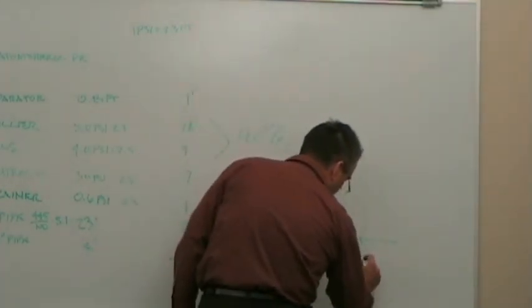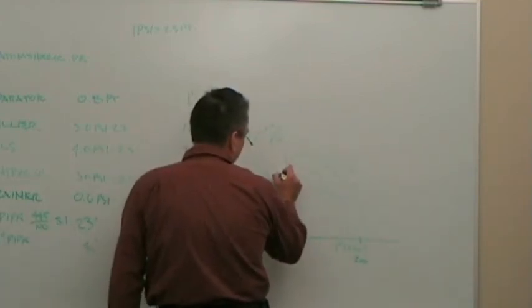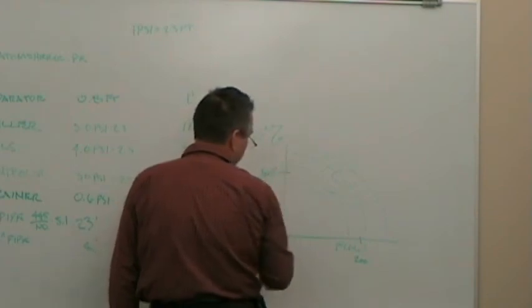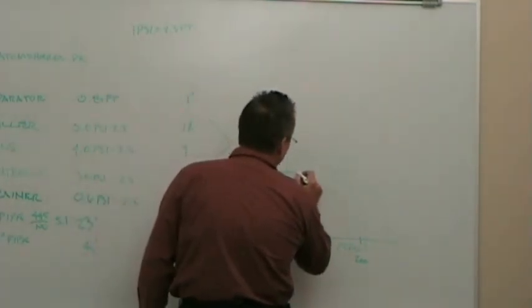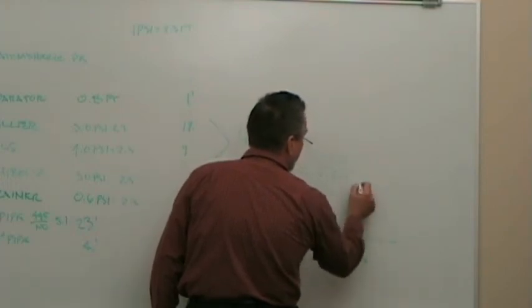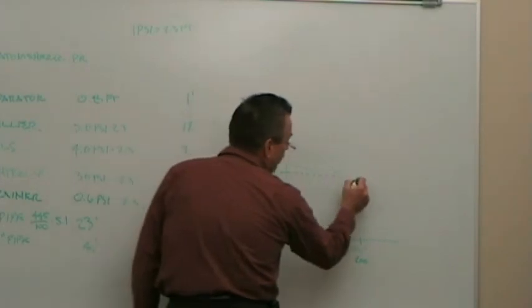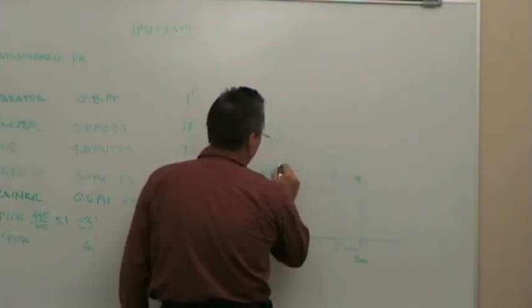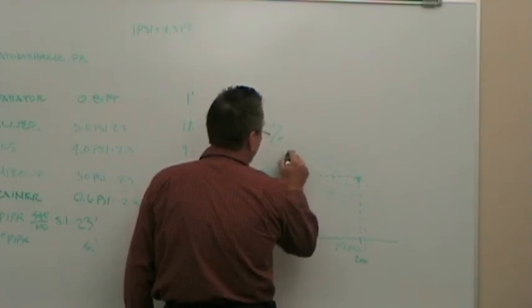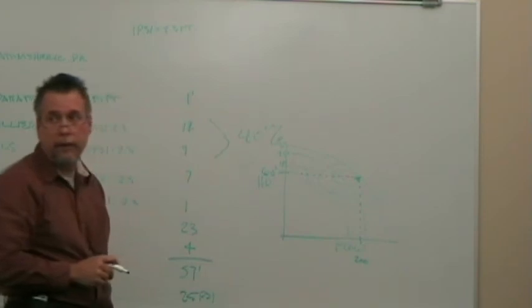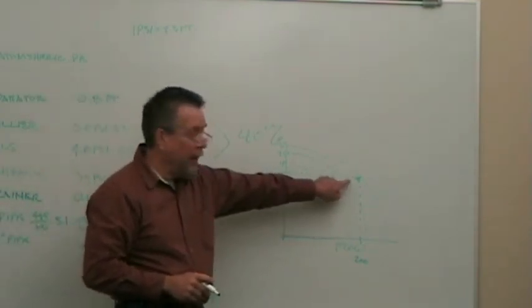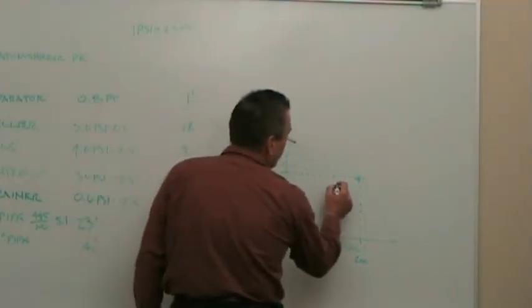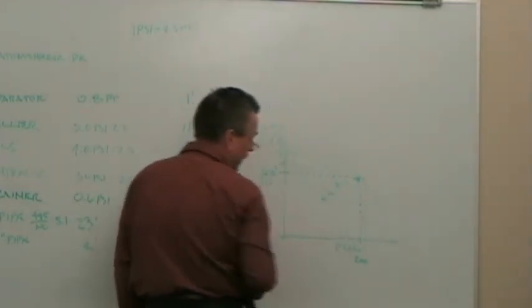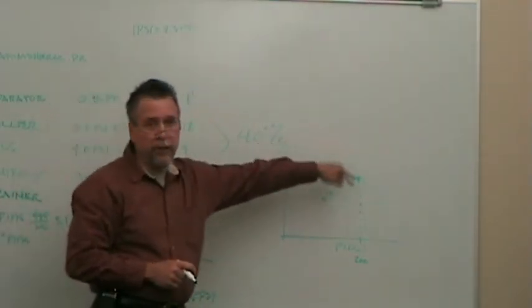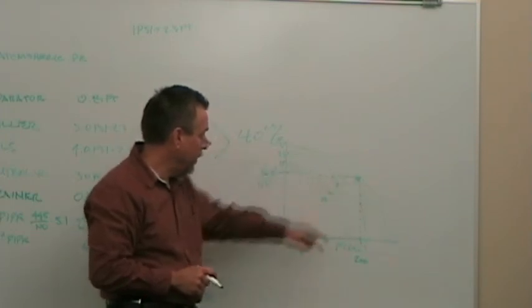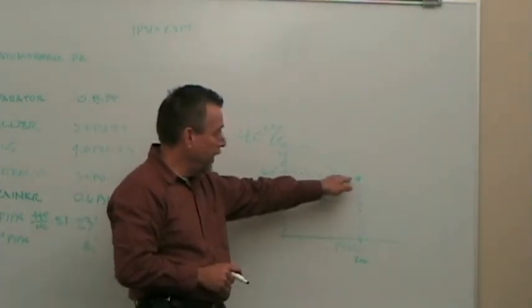So right here is 200 gallons a minute, and right here is, let's say, just 60 feet of head. If I had this particular pump curve and I plotted these lines, it intersects right there. Let's say this is a 4-inch impeller, this is a 4.5-inch impeller, and that's a 5-inch impeller. Right in the eye of the best efficiency, this is something like 75, 70 and 65% efficiency lines that show up on the curve. So I've got a pretty good selection here, right in the middle of the curve, right in the eye of the efficiency.